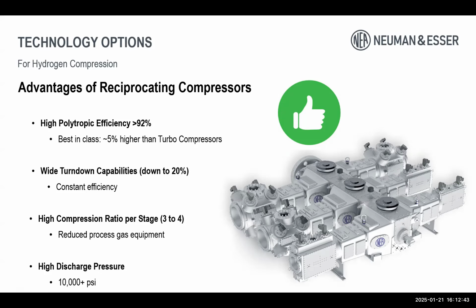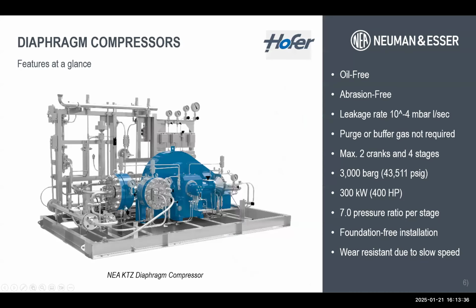So a lot of clients want to do what they call load following. If your electrolyzer, for example, is decreasing capacity, you want the compressor to decrease the power consumption proportionally. The reciprocating compressor can do that at constant efficiency. So that's a very important feature, especially for green hydrogen projects. You can have relatively high compression ratios per stage, 3 to 4. That means you have reduced process gas equipment like piping and coolers, and you can have pretty high discharge pressure on those machines, up to 10,000 pounds. A lot of times we compare different technologies for clients for their hydrogen projects, and we provide all the technical justifications for why to use reciprocating compressors. That's actually where I spend a good amount of my time these days.